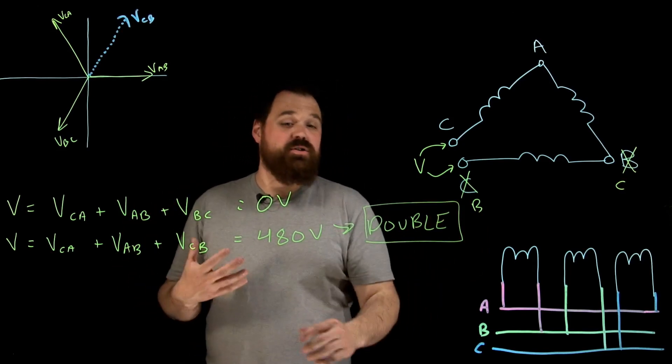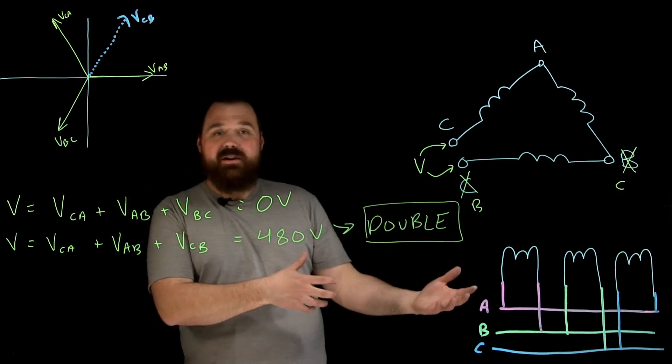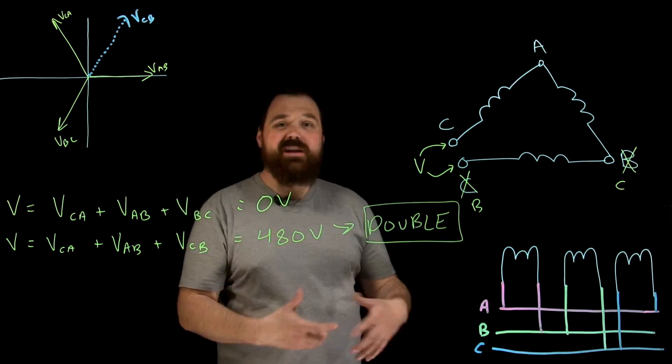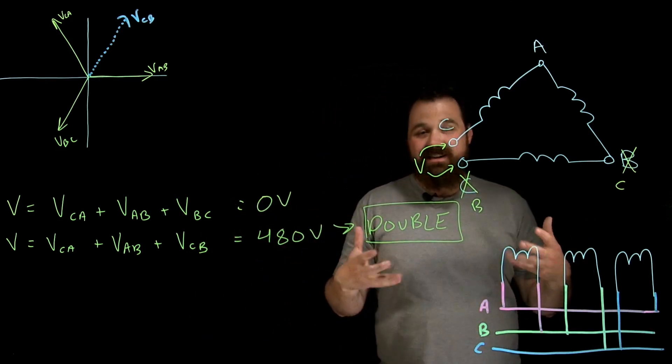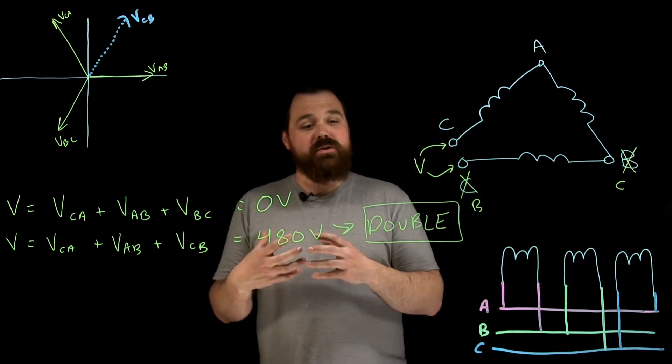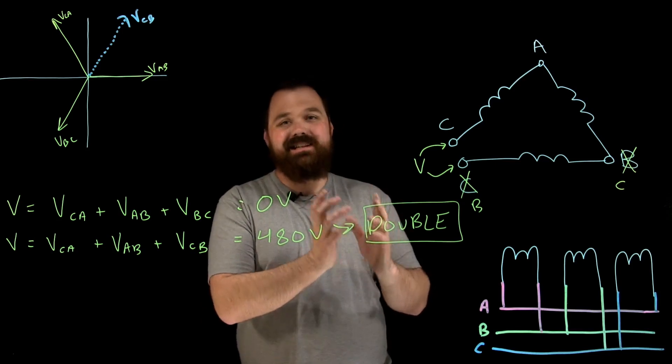So that's just a test that you would do when I'm gonna energize the secondary of that transformer. I double check. If it's a proper connection, I see that zero volts. If it's an incorrect connection, whatever my source voltage is or my rated voltages, I'm gonna see double that.